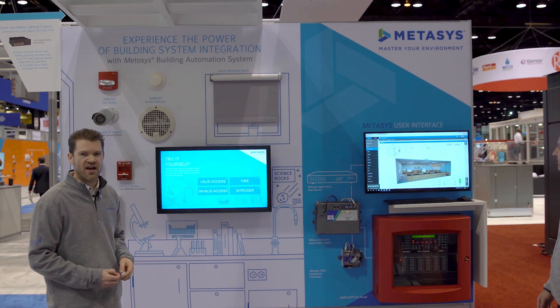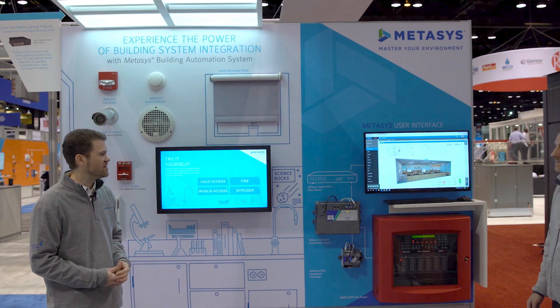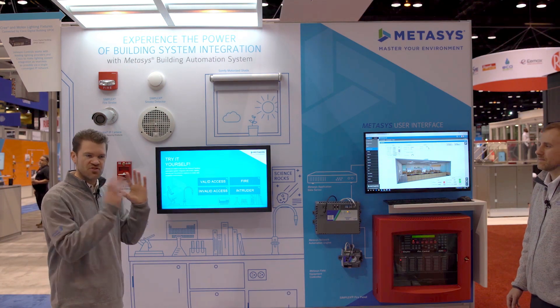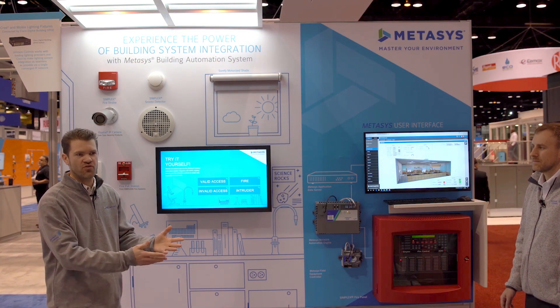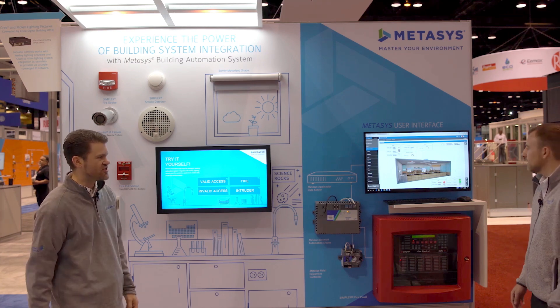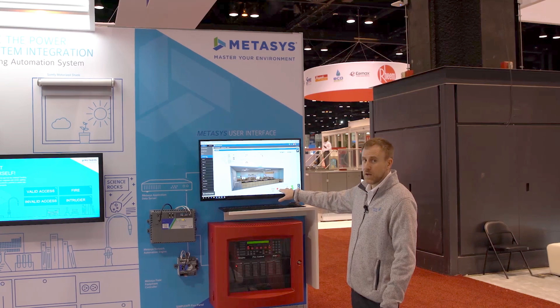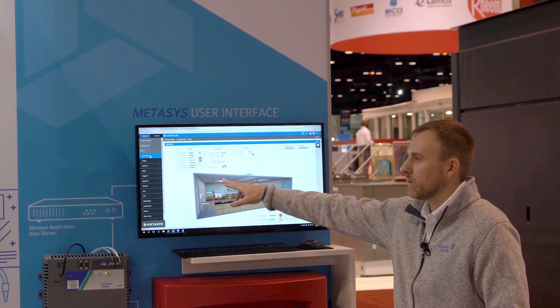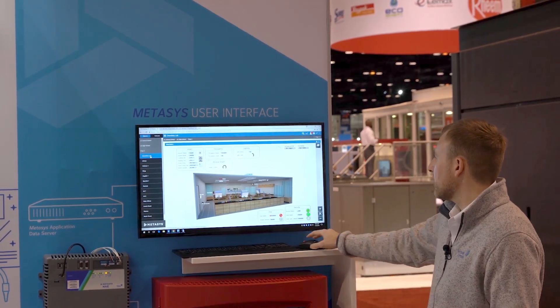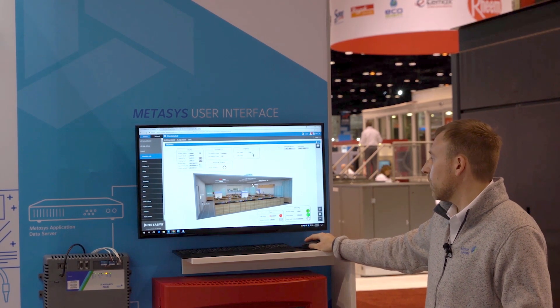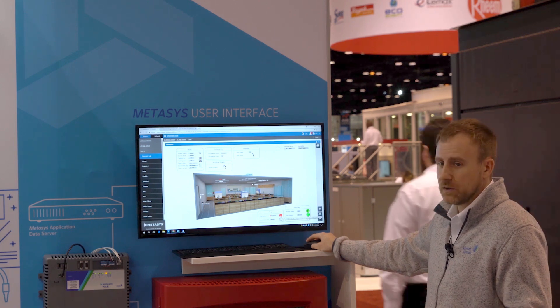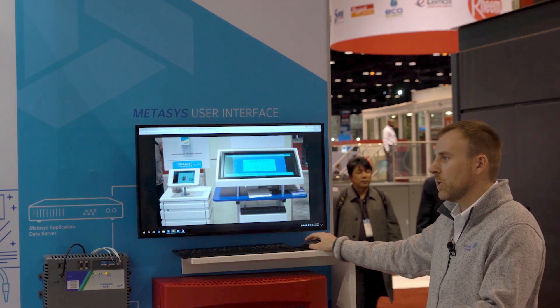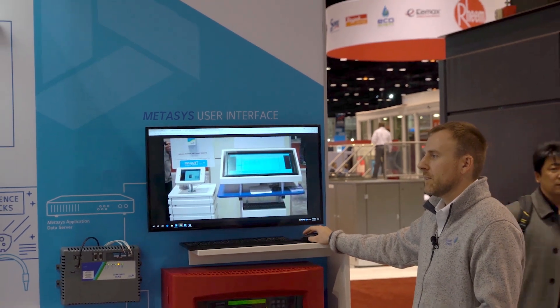Metasys already knows that somebody in the chemistry lab has pulled the fire pull station. Using that information, we can then automate the lighting fixtures and animate them to indicate which direction occupants should move to get out of the building safely. In the Metasys UI, we can see that the pull station indicator has turned red, so we know there has been an event there, and the strobe is also red in the graphic. The operator may also want to utilize the camera — they can click on the actual indicator and it'll take you right in to have a visual of what's going on in the chemistry lab, see if there's smoke, see what's actually happening, and have a more intelligent response.